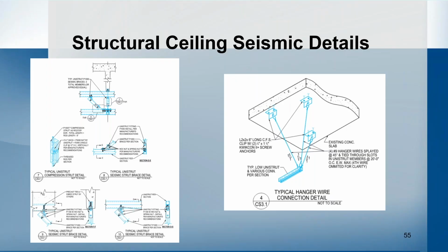And then detailing wise, it's going to be detailed one of two ways. Technically one of three ways. So if we have those precast tees, all the seismic bracing is going to be using strut members, going from your strut to strut with some rod and some diagonal struts as well. If you have either a concrete slab or steel beams, I said 3, I'm only showing 2. The other option, for the one on the right, would be connecting directly to steel. So you'd be using typically 9 gauge or even 12 gauge wire, depending on the seismic requirements. It'd be 4-way wire, and that would be what you would use to restrain seismic in that case.